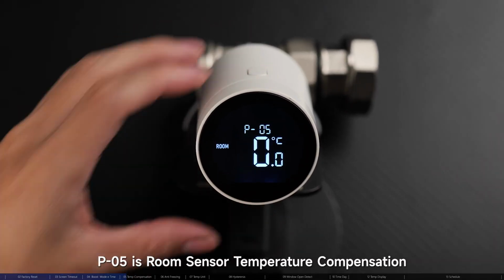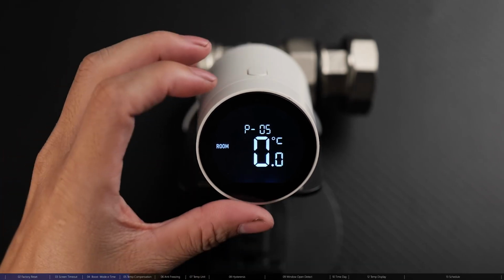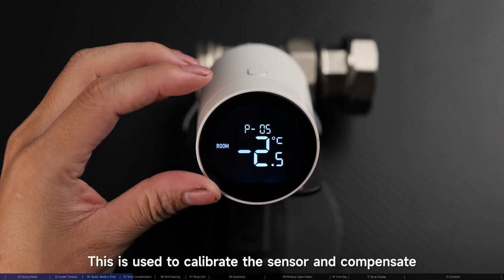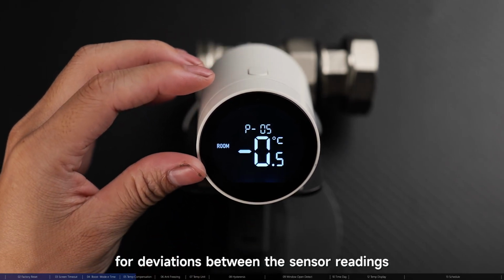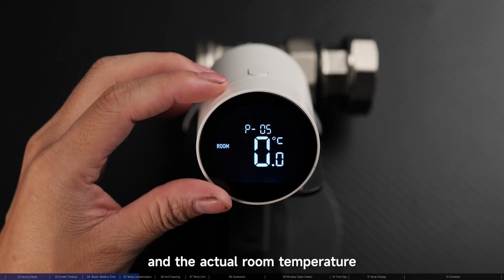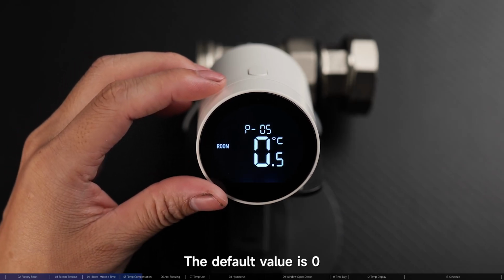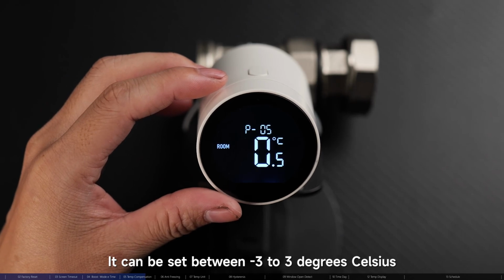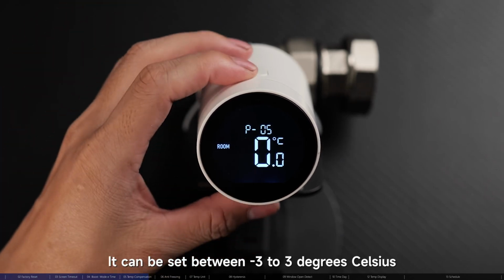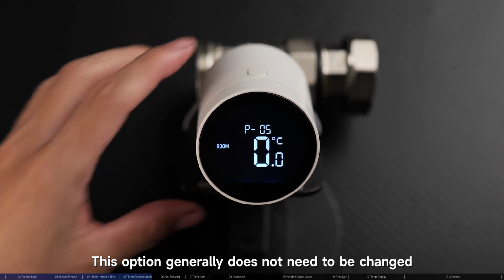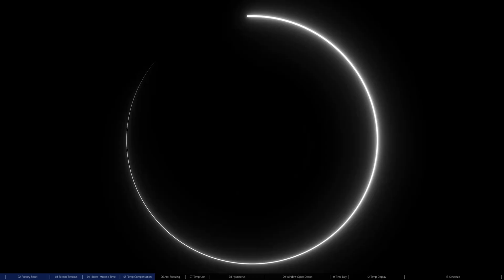P05 is room sensor temperature compensation. This is used to calibrate the sensor and compensate for deviations between the sensor readings and the actual room temperature. The default value is 0. It can be set between -3 to 3 degrees Celsius. This option generally does not need to be changed.